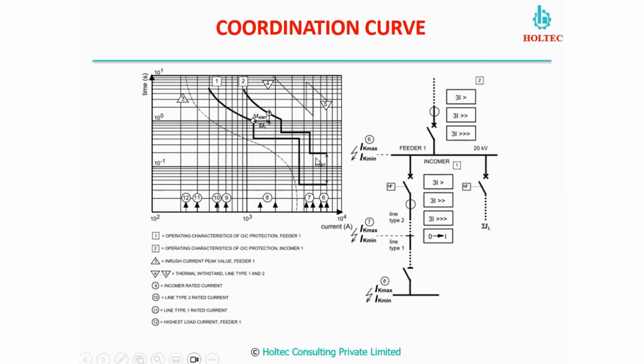In our system, when we do the relay coordination, there will be a minimum grading time because of some limitations of the operational characteristics of the circuit breakers, the relay and other associated equipment. Normally, with new numerical or microprocessor based relays, we still recommend at least 150 milliseconds of time grading. So we have to achieve a minimum of 150 milliseconds or more to ensure that relay number 2 should not operate for any fault which is happening here.